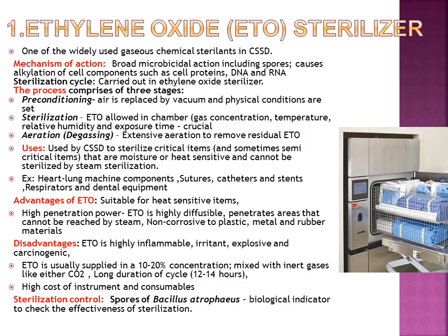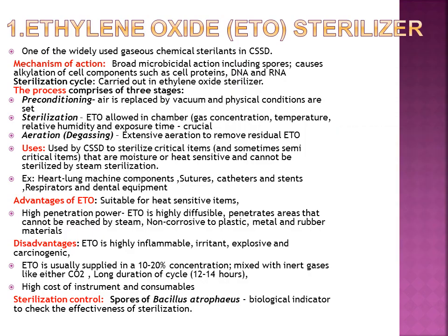Advantages: suitable for heat sensitive items. It has high penetration power, highly diffusible, penetrates areas that cannot be reached by steam, non-corrosive to plastic, metal and rubber material. Disadvantages: highly inflammable, irritant, explosive and carcinogenic.